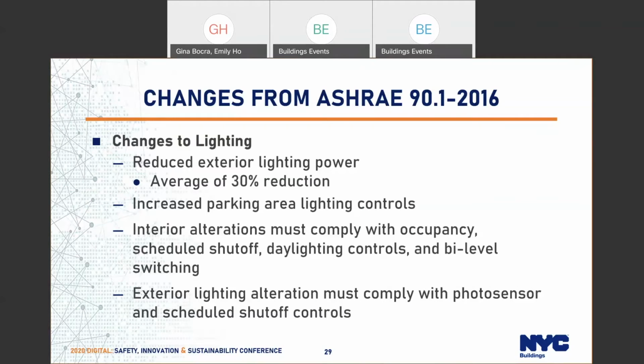Other changes in controls: parking area lighting controls. There's now a requirement, as I was mentioning, this is the ASHRAE language that the state adopted into the ECC. If you have an outdoor parking area, there are now occupancy controls required on certain lighting fixtures in that space.